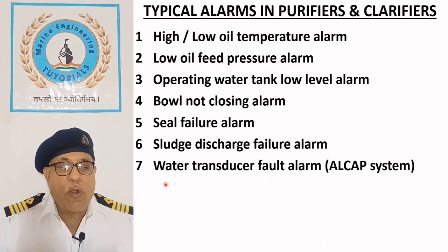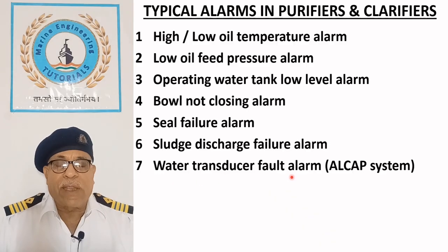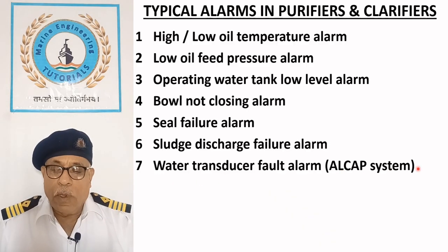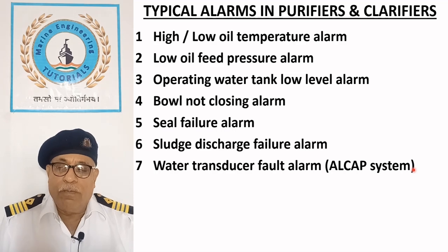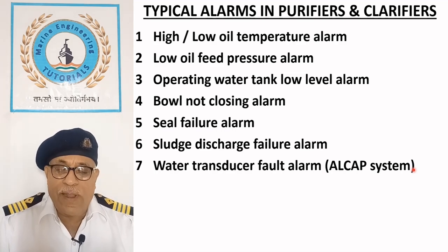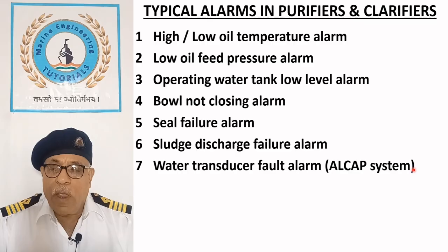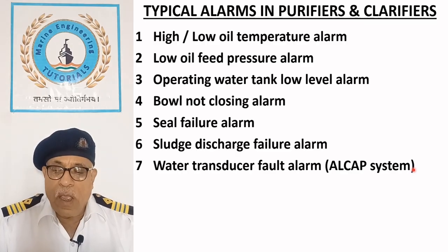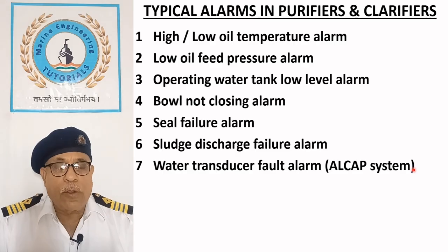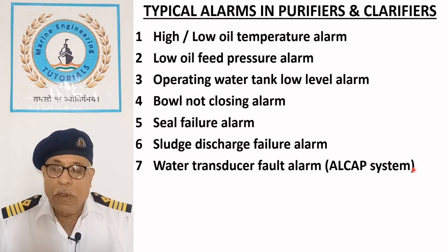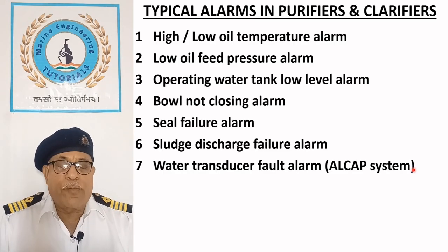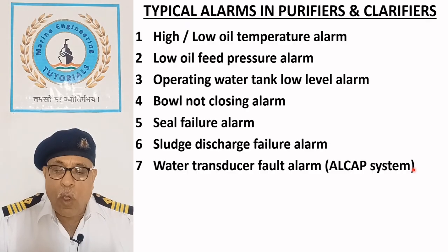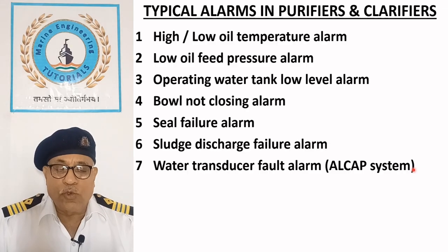Water transducer fault alarm in ALCAP system. In the ALCAP system, if the water transducer fails to provide an output signal, the control panel initiates a water transducer fault alarm. This may result from a broken connection or a defective transducer.